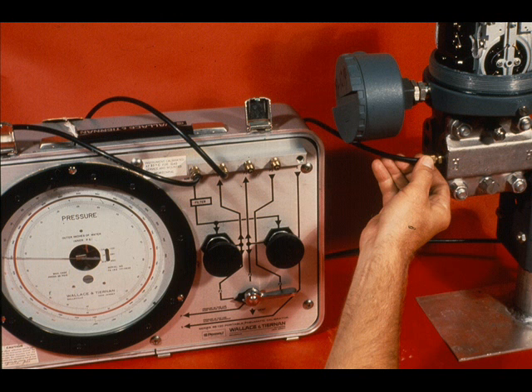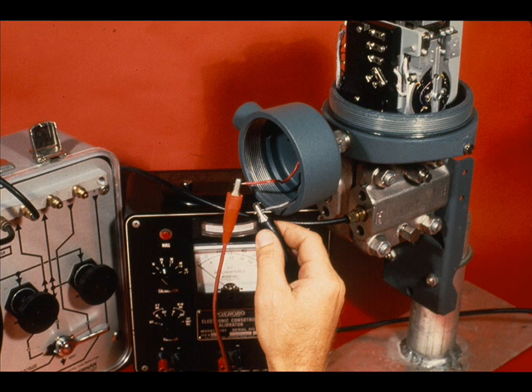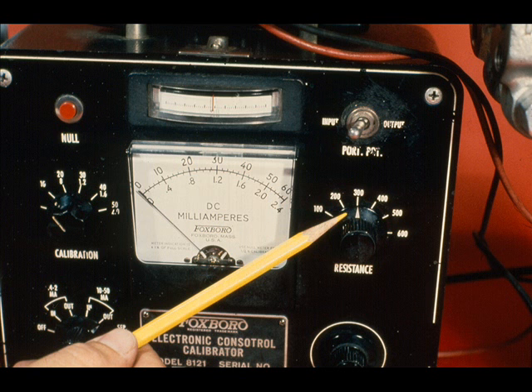To proceed with the calibration, connect the variable pressure source to the high side of the transmitter. Here, we are using a pneumatic calibrator. The low side of the transmitter must be vented. Connect the Foxboro 8121 or equivalent calibrator to the transmitter. Set it for calibrating a 10 to 50 milliamp force balance transmitter. The transmitter is connected to the output terminals.